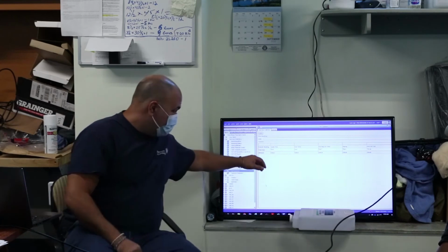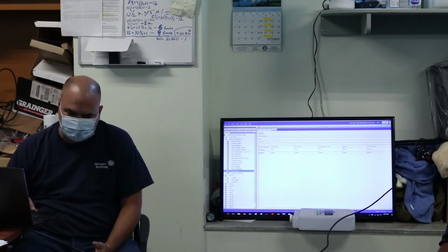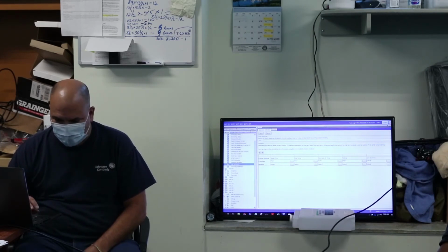And these are the points so far that we've chosen to monitor in this summary: the supply air flow, the zone temperature, the discharge air temperature, the heating valve, and the zone set point. Now I think we have room, we could add one more, so let's add another one to show you how to do it. So let's add the supply flow set point so that we know the amount of air that we're looking for.